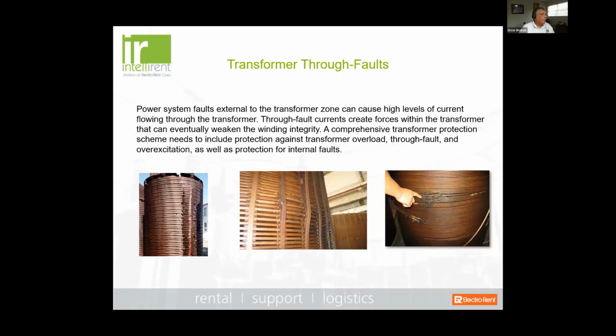Okay, so transformer through faults, your power system faults, these are faults that are external to the transformer zone and can cause high levels of current flowing through the transformer. And these forces within the transformer can eventually weaken the winding integrity. A comprehensive transformer protection scheme should include protection against thermal overload, transformer overload through fault and overexcitation, as well as protection from external faults and internal faults. Okay, so the protection is there.